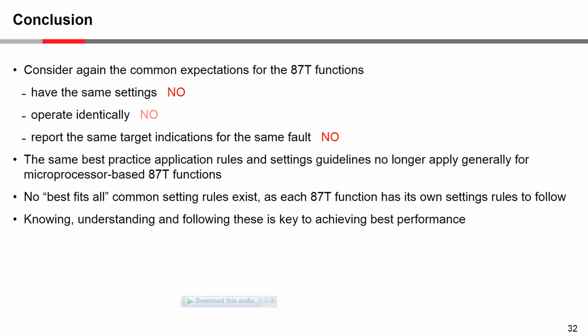And will the relay report the same target indications for the same fault? And there it's no, because you can see if you chose the delta side as the phase reference, you would get 2 phases operating, whereas if you chose the Y side as the phase reference, you would get 3 phases operating.